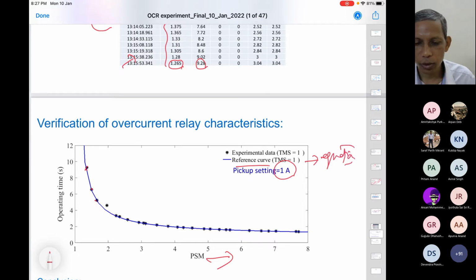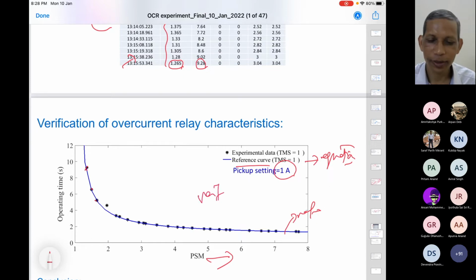The equation data there that you should follow. So this solid line is nothing but a reference. And the dots, or stars you can say which you mark, are nothing but the experimentally verified points. So what you see is an identical characteristic to the reference curve, which is based on the equation, and the corresponding simulated one after injecting and the actual tripping by the relay. The star marks here, they are following the curve. It means that the relay is good one. So that is the verification we are talking about here.